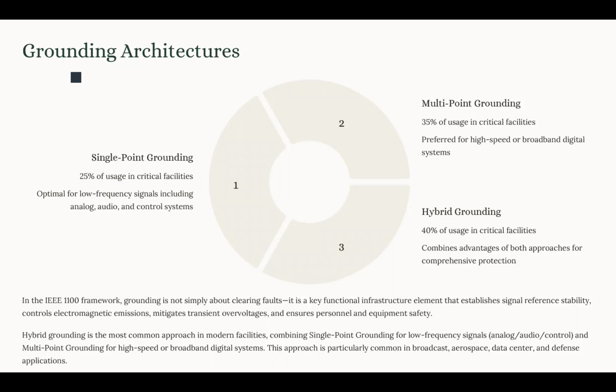Now we have three types of architecture. One, as we mentioned, is single point grounding, when all the equipment and the signal grounds terminate at a single common bonding point. We have multi-point grounding, which we already covered. It is when equipment is grounded at multiple points, normally arranged as a mesh or star pattern. And we have hybrid grounding, which combines single point and multi-point grounding. We already talked about that. I don't want to over-explain those concepts, in favor of saving some time.